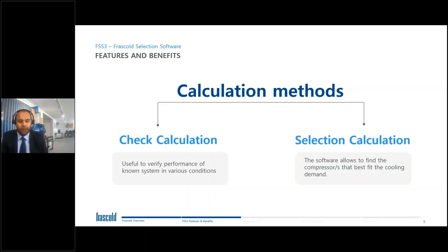Otherwise, with selection calculation, you ask the software which is the best compressor that fits a given condition and the cooling capacity required for that condition. Usually, if you start from a blank sheet, it is better to use selection calculation, see what the software gives to you, and then with check calculation, refine the selection.